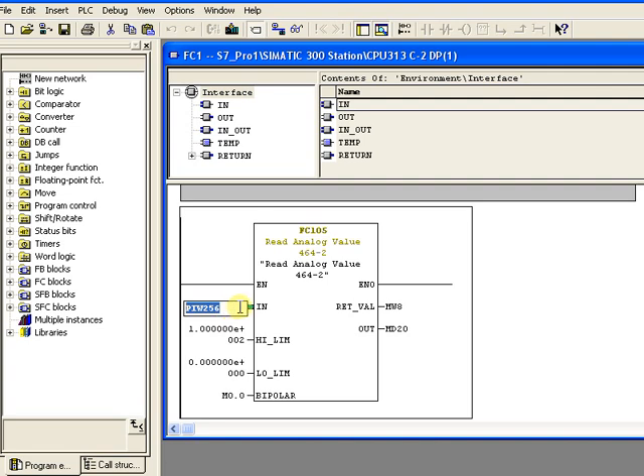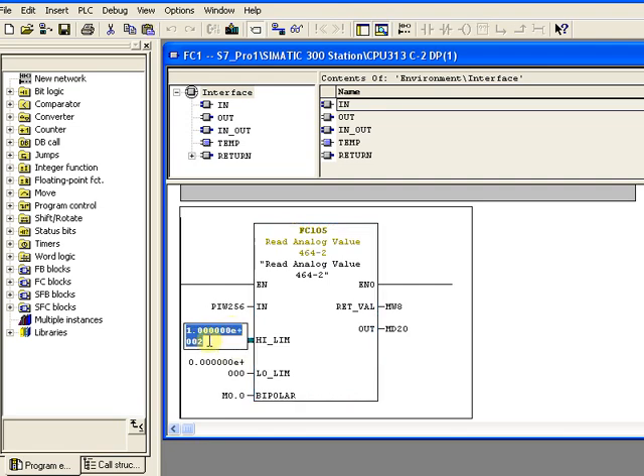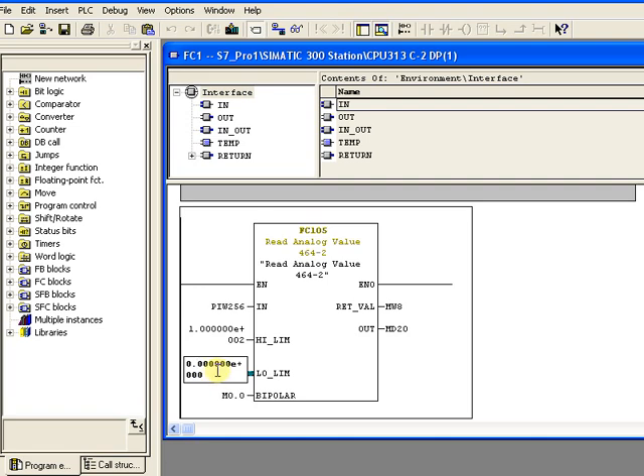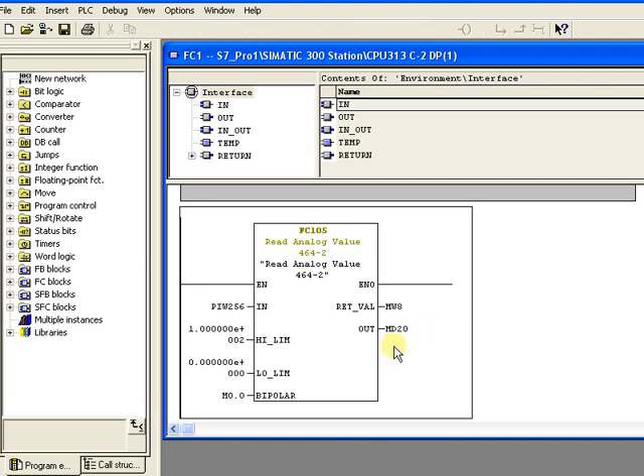The first input is the input address — from this address the scaling function will read the input. Then this is the higher limit: the higher limit of the sensor is 100 degrees Celsius, so I give 1.0000E+2 (which equals 100). The lower limit is 0. We will keep the output of the scaling function to memory address MD20 — M for memory, D for double — so MD20 is just a memory address where we store the scaled value.